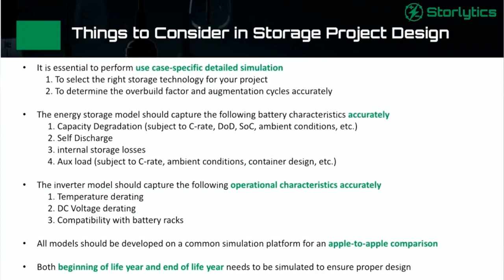Your inverter models need to represent temperature derating, DC voltage derating, compatibility with battery racks. So when you're doing the simulation, you need to put together a system that is actually viable. You need to look into those as well. Most important of all, this modeling that you're doing, comparing different technologies, needs to happen in a common simulation platform for an apple-to-apple comparison. Otherwise there are just so many differences, and those are difficult to capture if you do not have a validated model in a common platform.